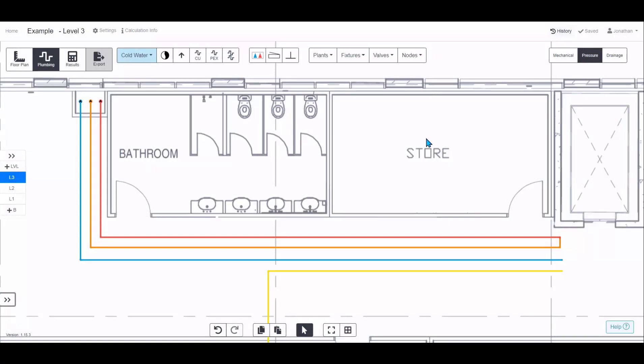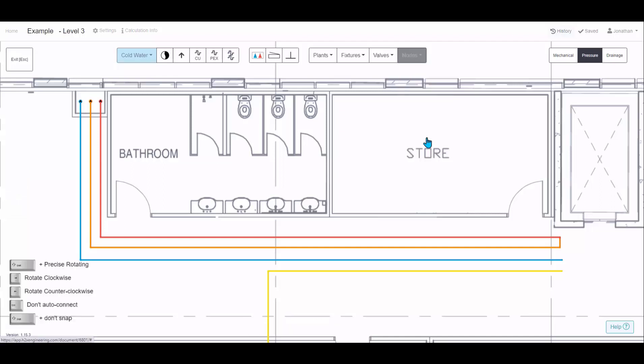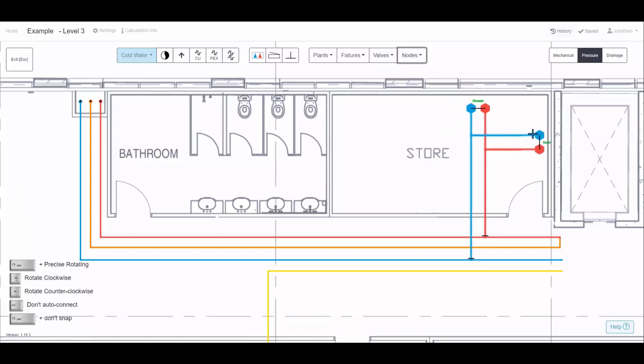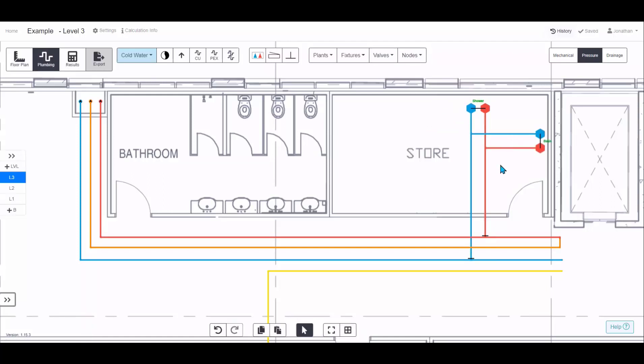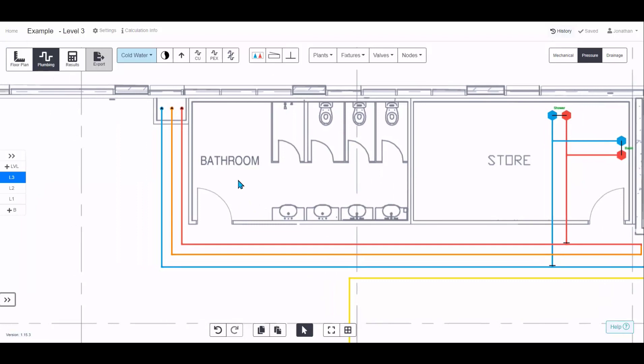Nodes are a great way to get results quickly. Instead of adding individual fixtures and connecting them all, you can choose a node — for example a shower in one area or a basin in a corner — and it will snap to the nearest pipes. For calculations it looks up the fixture units or loading units to size the pipes.